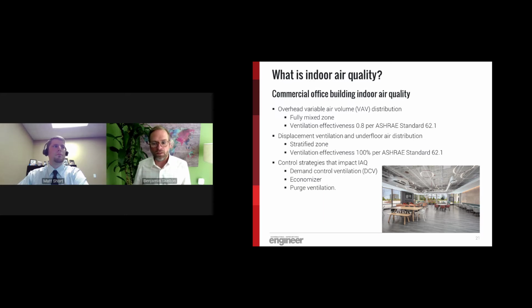When we look at another type of system, displacement ventilation, often referred to in offices as underfloor air distribution, this tends to create a stratified zone. So the air is introduced at the occupant level, typically at the floor or at the desk level, and comes directly into the occupant space. So they're getting fresh air. They're getting 100% of the effectiveness of that. And the air above the occupied zone, maybe 6 foot or so, is stratifying. It's not being mixed, or it's being extracted. But there are other systems out there, but those are 2 examples of that.